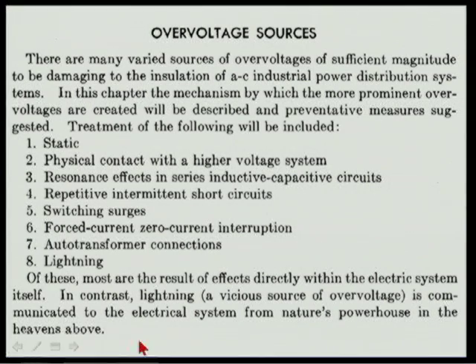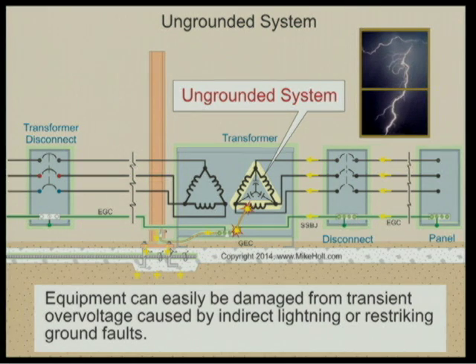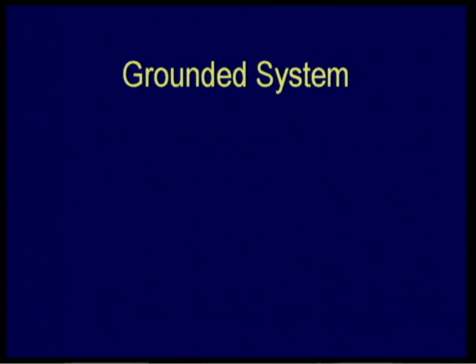Treatment of the following will be included: static electricity — you need to ground that; physical contact with a higher voltage line; resonant effect with series inductive-capacitive circuits; repeating intermittent short circuits — that's the re-striking ground faults; switching surges; forced zero current interrupting. I have no clue what most of that is talking about because it's the problems associated with ungrounded systems. We started the industry with ungrounded systems and got a lot of problems with overvoltage. So Beeman suggests you need to go to a grounded system.